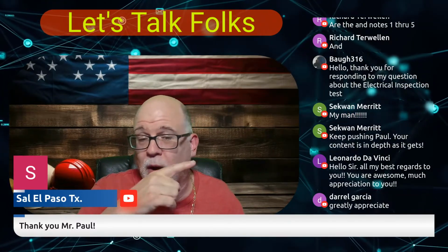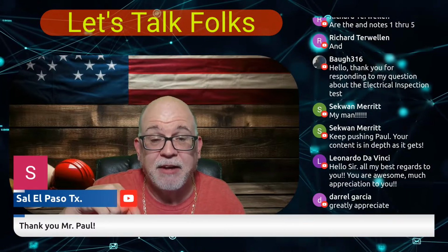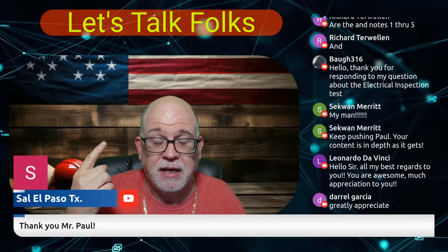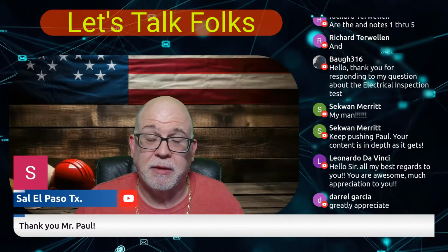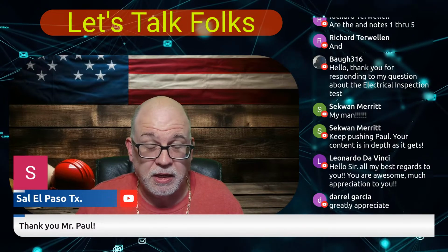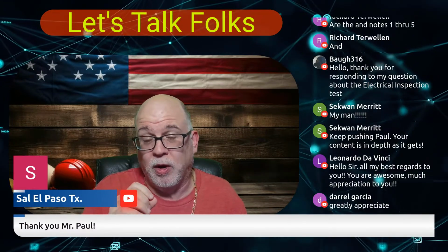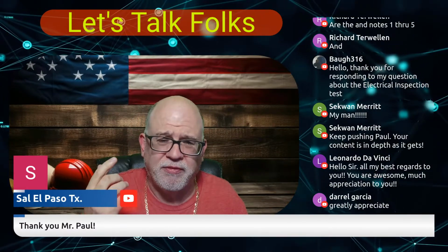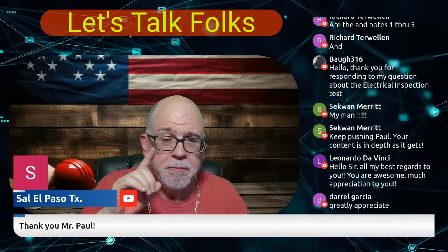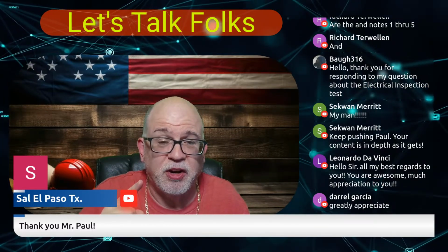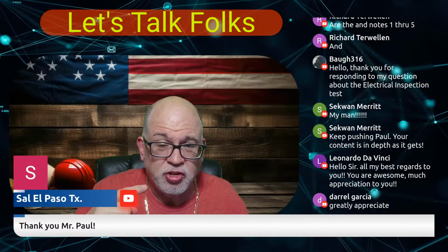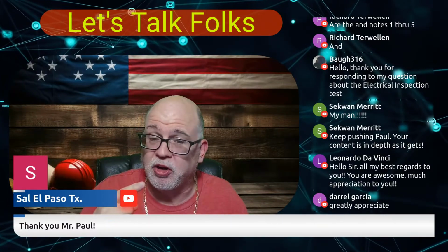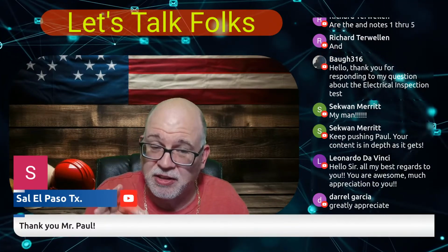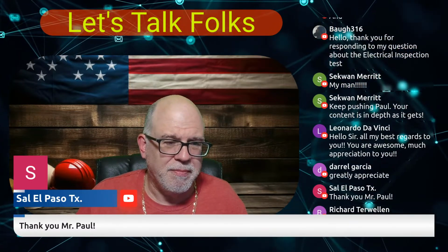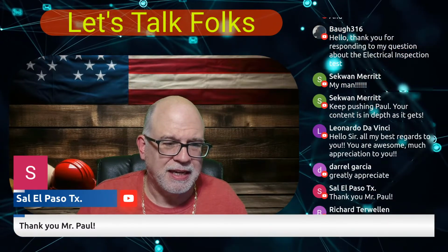And don't forget to go watch my video that's on today at 4 o'clock. That'll be streaming. Make sure you go watch that. That's talking about motor branch circuits and not the normal, whereas people know that you just do 125% of the FLC. But we want to make sure that you understand that if there is an adjustment or correction due to ambient temperature or more than 3 current carrying conductors, you got to take that into consideration as well. So we're going to cover that today. So make sure you check that out, okay?